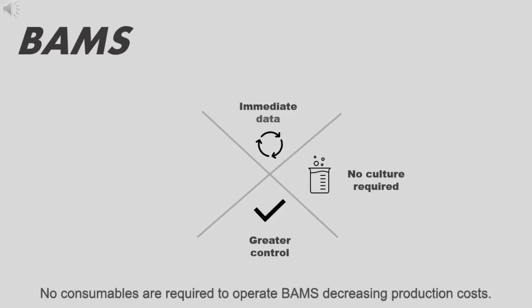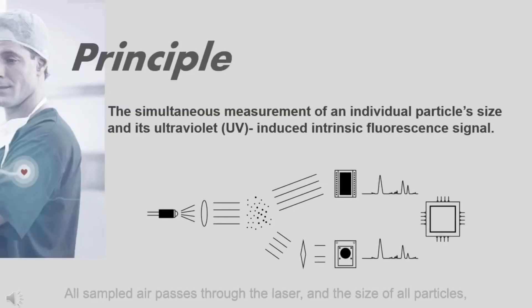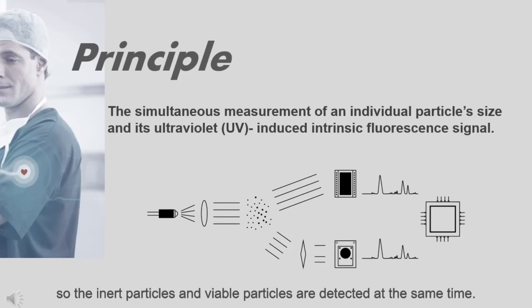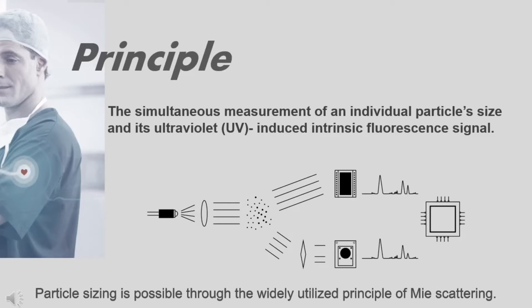No consumables are required to operate BAMS, decreasing production costs. All sampled air passes through the laser, where the size of all particles, both inert and viable, is measured. BAMS detects size and fluorescence simultaneously, so inert and viable particles are detected at the same time. Particle sizing is possible through the widely utilized principle of Mie scattering.